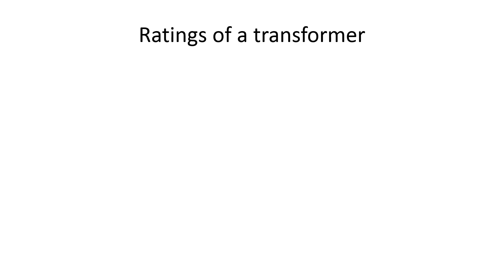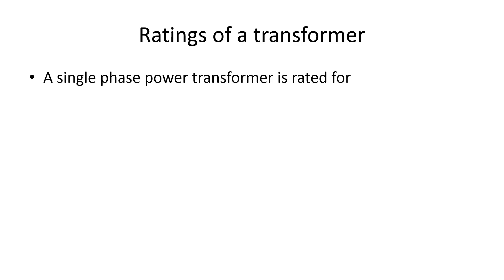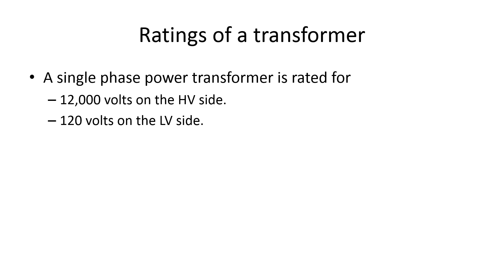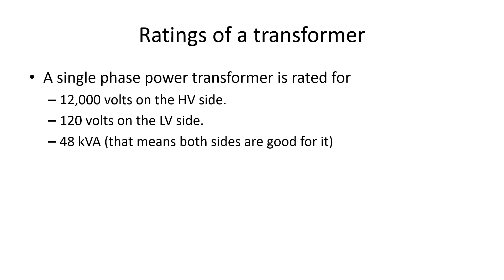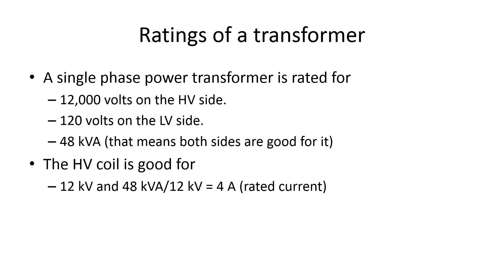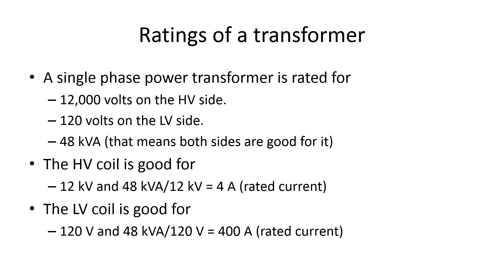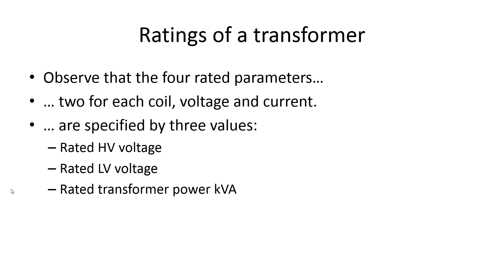Let's consider a specific single-phase transformer. It is rated for 12 kV on the high side and 120 V on the low side, and can transfer 48 kVA — its rated power. The rated current of the primary is 4 amperes and the rated current of the secondary is 400 amperes. Notice that we used only three parameters — two voltages and one power — to compute all the others.